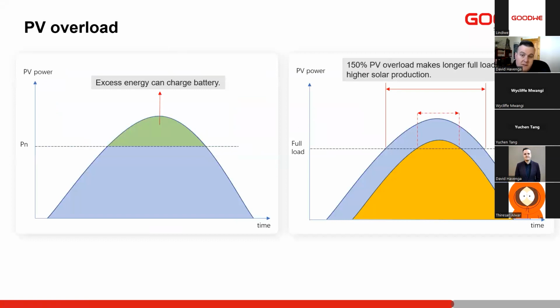What this oversizing does, as you can see in this graph, is that typical PV oversizing will just make us reach our peak sooner in the morning and stop the peak later in the day, so you'll have a flat curve here. But with our oversizing, as you see, all the excess energy can be used to charge the batteries, so you don't lose this energy. With typical oversizing, you would lose all of this energy during the peak of the day.